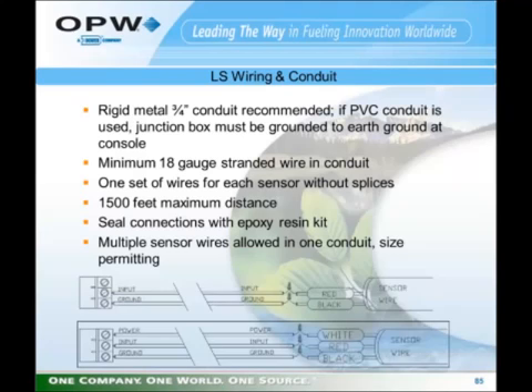All of the EECO sensor installation requirements do not require shielded cable for sensors. What we require is a minimum 18 gauge stranded wire to be used for sensor connections. Of course, this wire must be gas and oil resistant. One set of wires for each sensor with no splices. 1,500 feet maximum distance. As in the probes, we instruct you to seal the connections with an epoxy resin kit. As with the probes, multiple sensor wires are allowed in one conduit, size permitting. You're not allowed to daisy chain sensors in an installation.